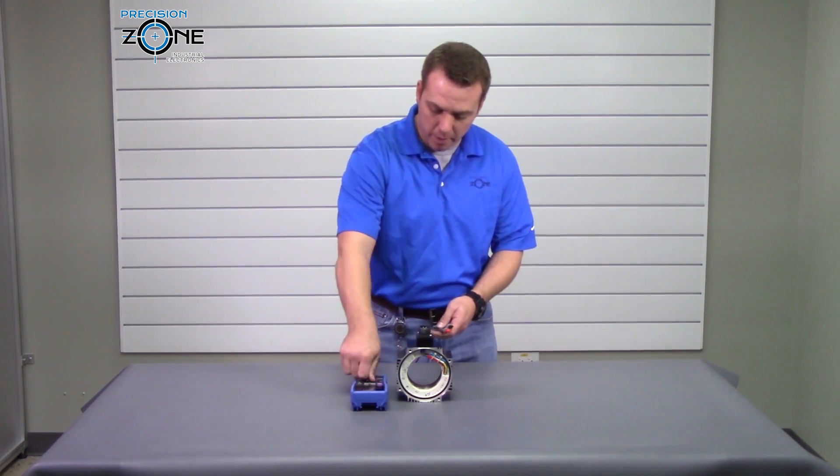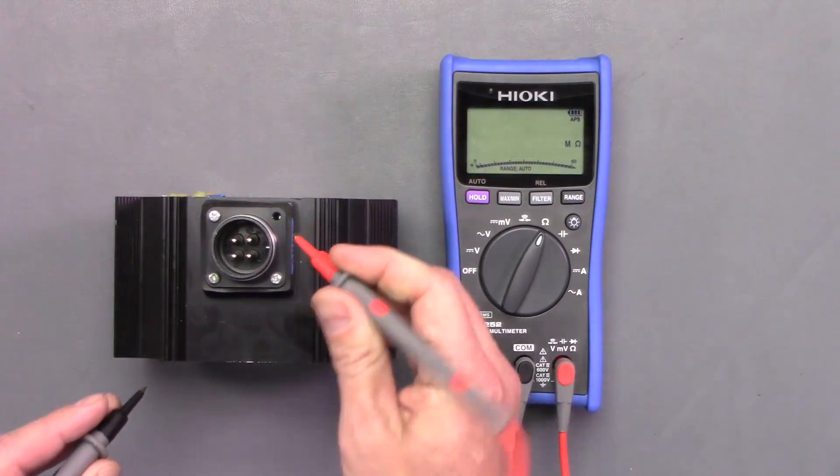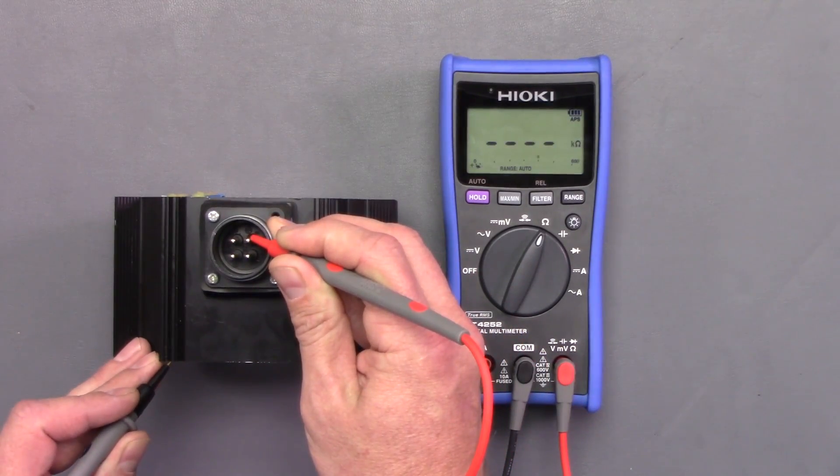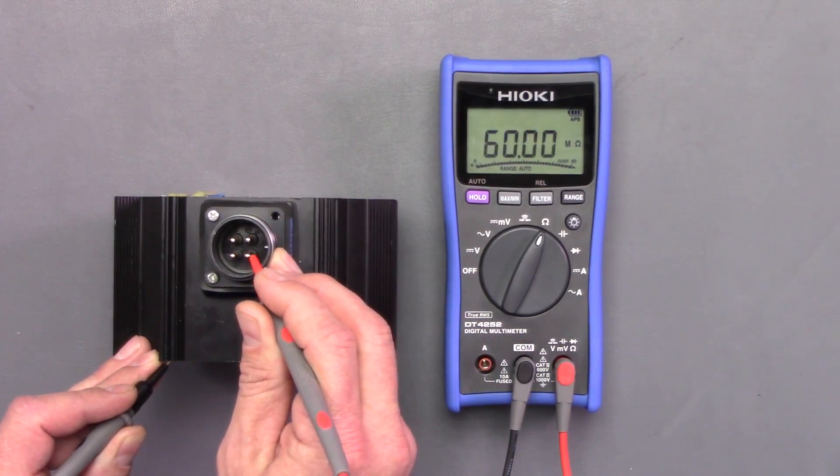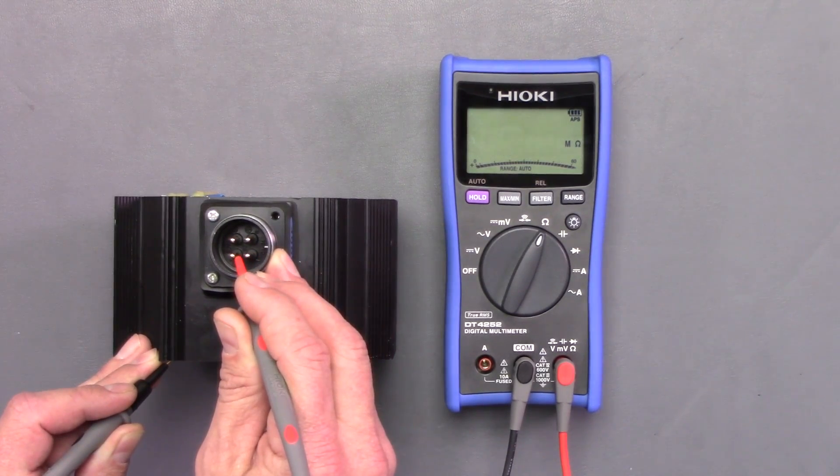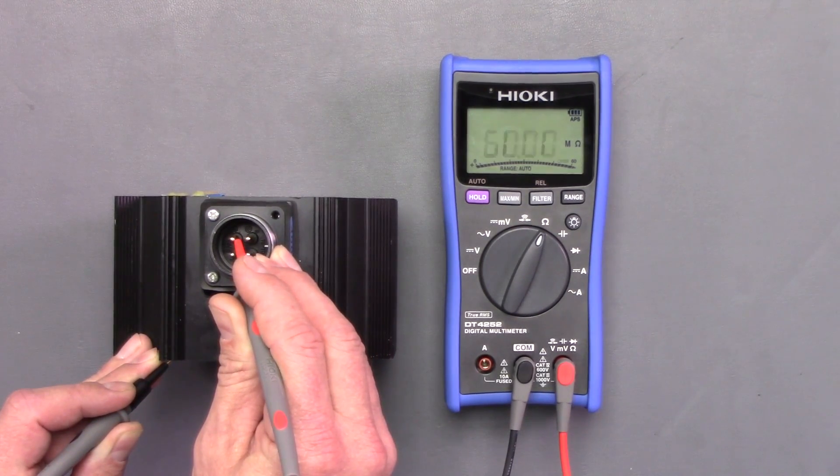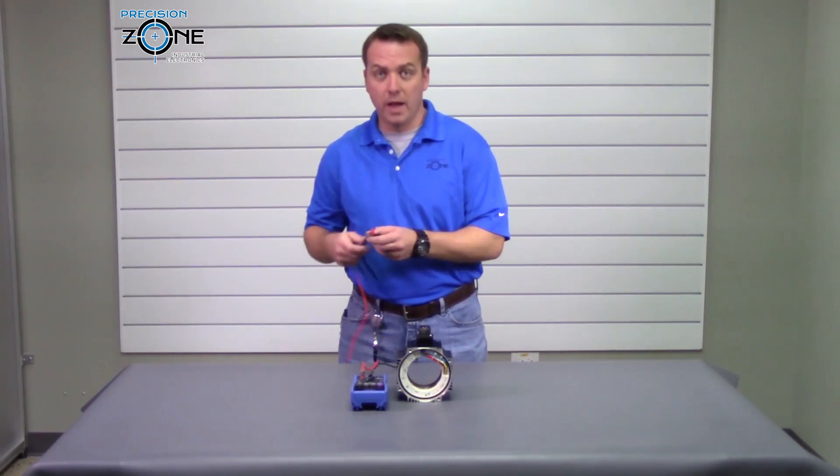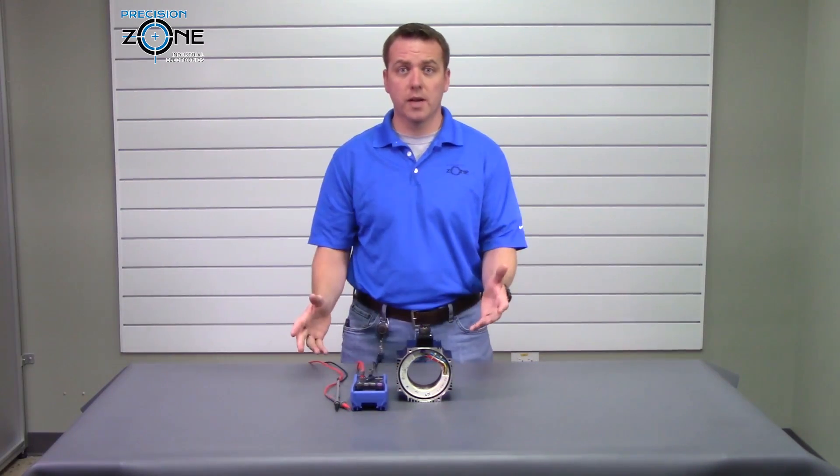So I'm going to go ahead turn my meter on. I'm going to check to make sure I have a good ground and I do and I'll go from U, V, and W and we don't have any continuity so that's great.